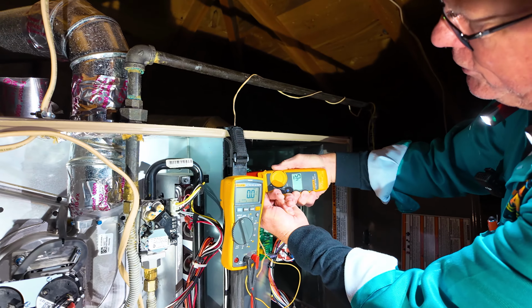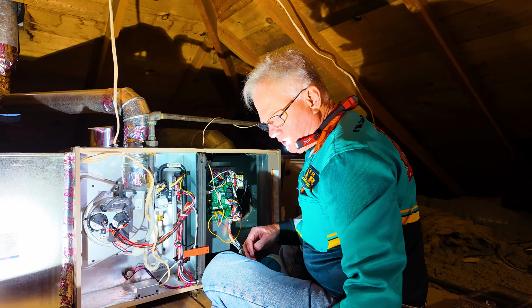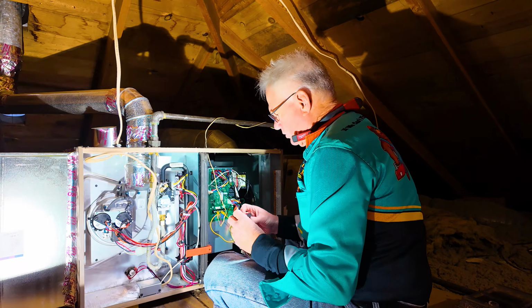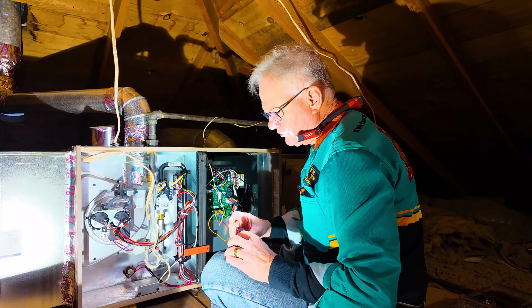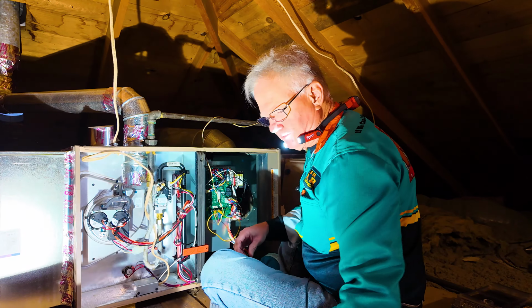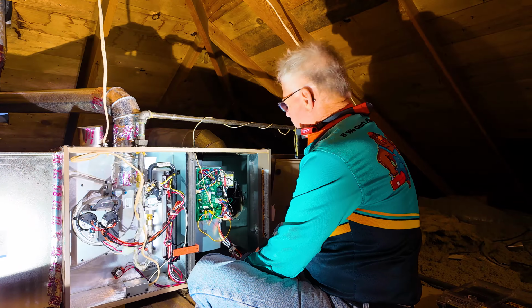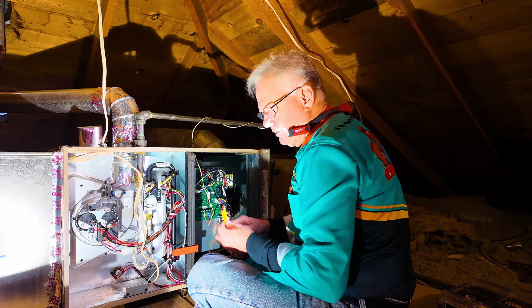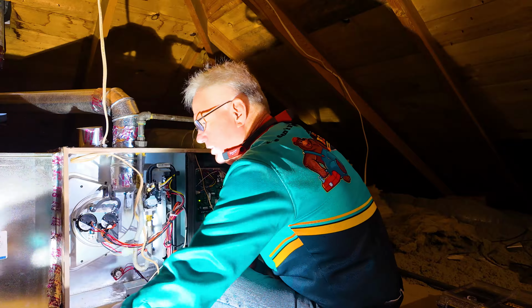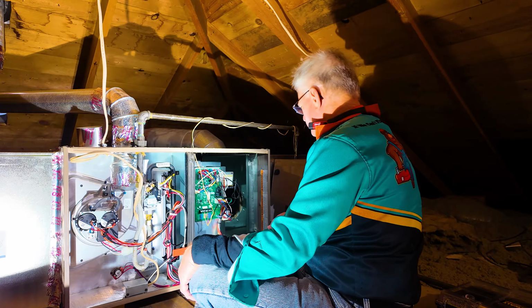We're good. All right, so we're done. So I don't know what was causing the issue, but more than likely it was that dirty, corroded looking flame sensor. And now that the flame sensor's been cleaned, we're just letting it cycle, watching it here, and there's really nothing else of concern. It seems like it's running fine. I don't need to jumper it because it's already calling for heat by the thermostat on its own.